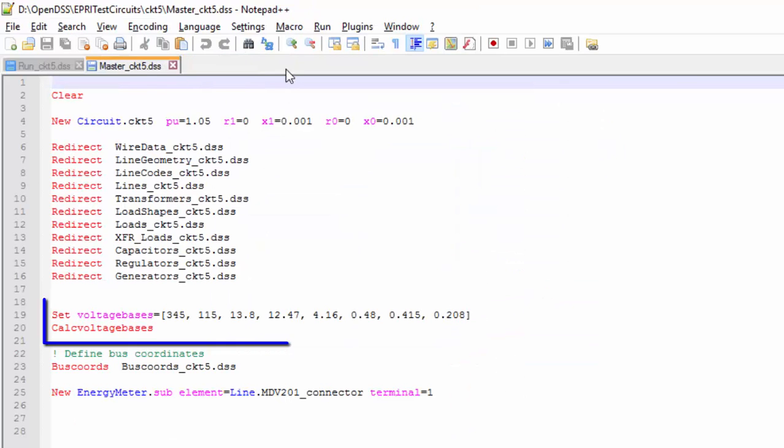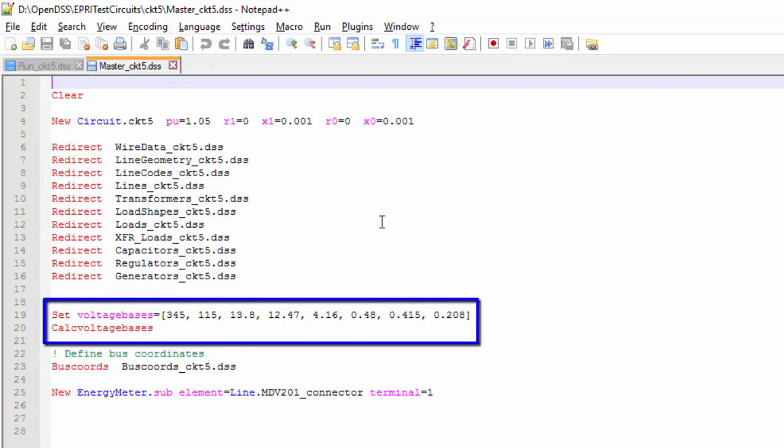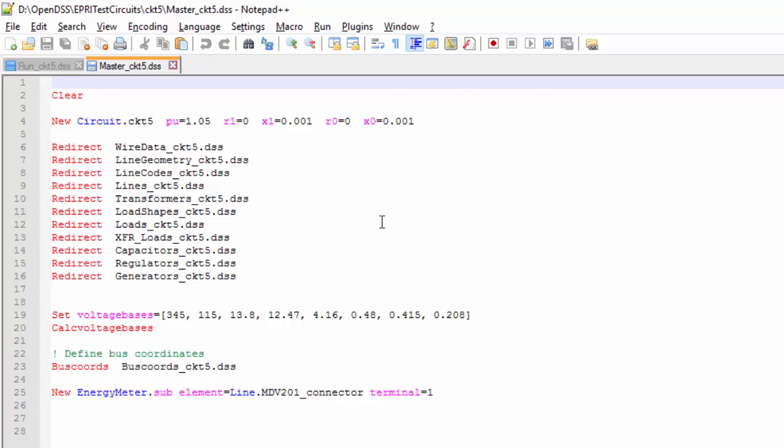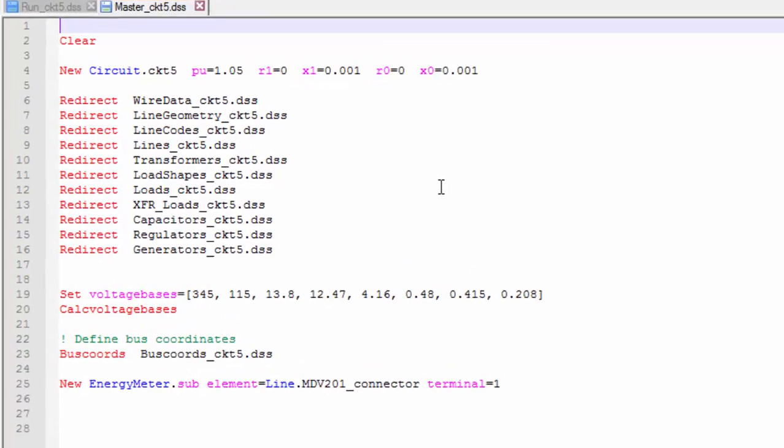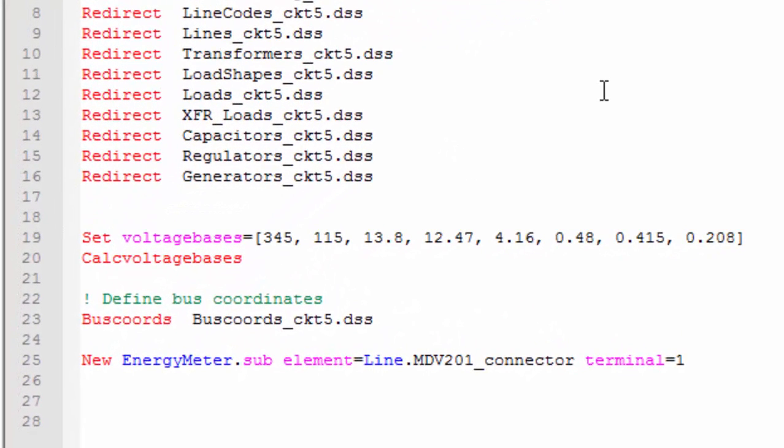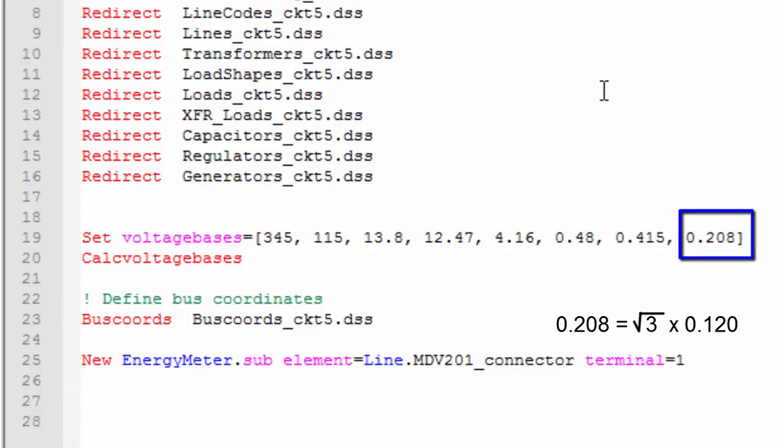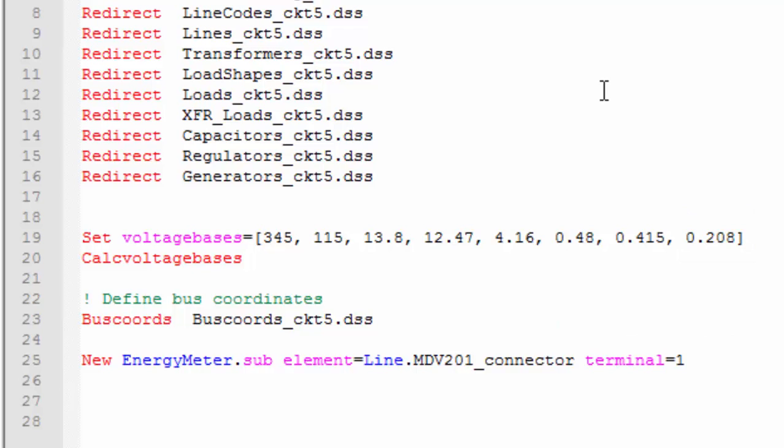The next two line commands are SETVOLTAGEBASES and CALCVOLTAGEBASES. The first one is where we define all line-to-line voltage levels in the system, in kV. Actually, in this example, there are more than necessary. For instance, there is no element with 0.208 kV line-to-line voltage, which would mean a 0.12 kV line-to-ground voltage, considering that we are in a three-phase system. Now, I got a question. Where is the 0.24 kV for the loads?